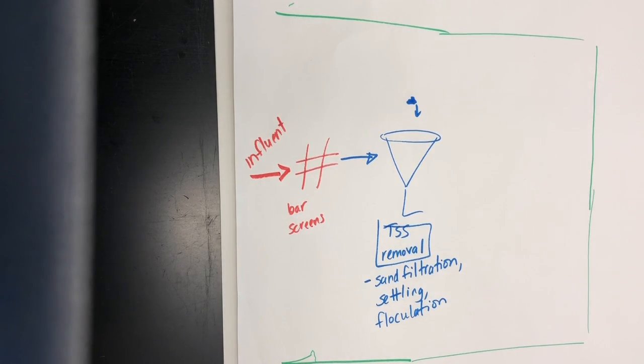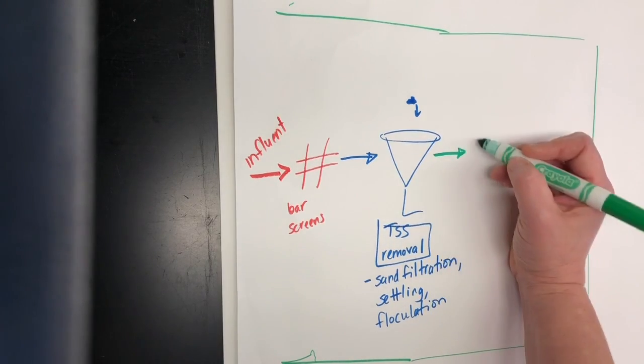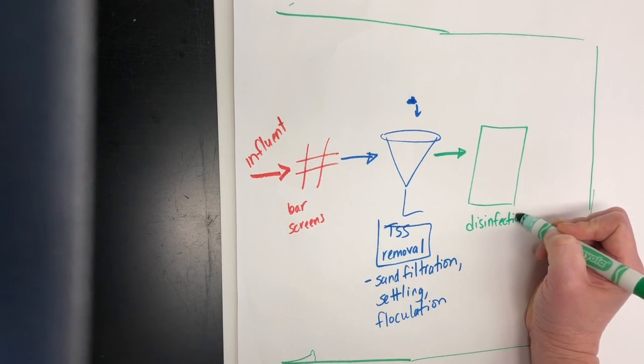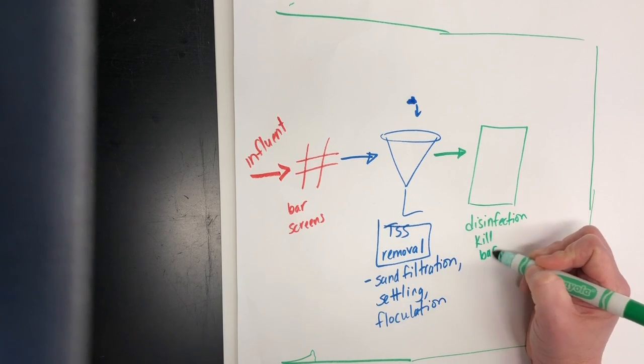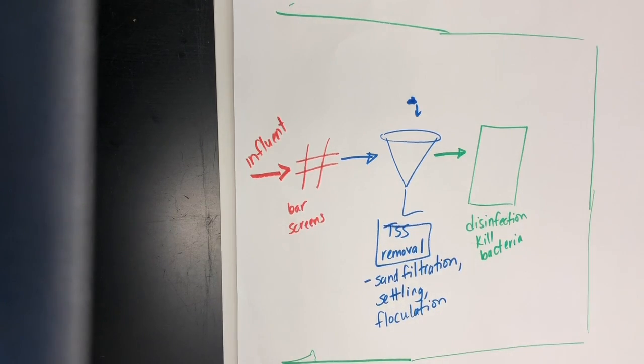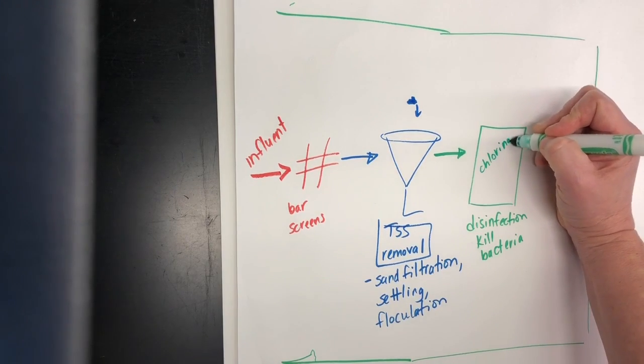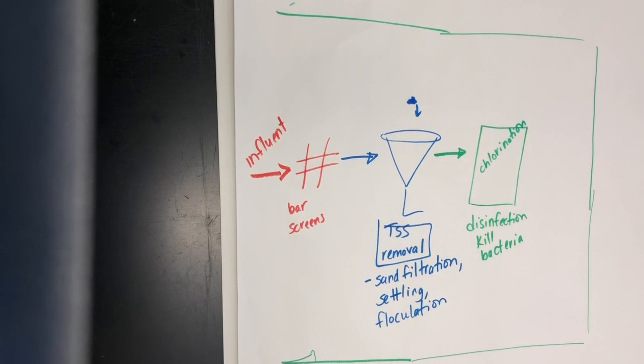Then the next step in the process is going to be essentially some sort of disinfection, okay? What is disinfection? That is, kill the bacteria. They don't just kill, some bacteria is good. In fact, a lot of bacteria is actually good, but in the end, they have to kill bacteria. How do they kill the bacteria? They could add chlorine. Typically, they'll add chlorine because that's the cheapest, and they'll chlorinate, and then they'll remove some of the chlorine, which is called dechlorination, and leave just a little residual behind, because too much chlorine wouldn't be good, but leaving a little bit helps in case later on something maybe gets into the water system. It could theoretically protect us.